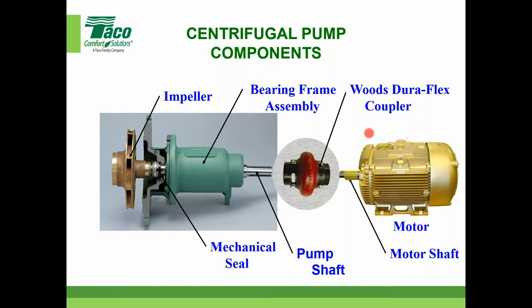We have standardized on Woods Duraflex coupler. Very good for variable speed applications, which is 80% plus of the market. I'll show you a picture of another one very shortly as well. And notice the motor, mostly all premium efficiency now.